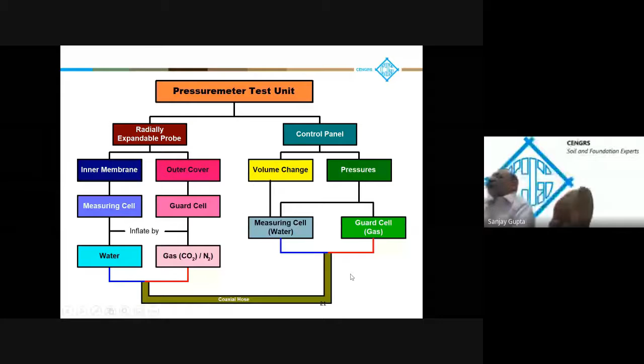So what are the steps involved? For air calibration, you expand the probe in air. Some pressure will be required to expand the membrane, as I just explained. The net pressure on soil is the difference between the measured pressure in situ and the pressure for expansion in air for a specified volume. That's, I think, quite clear.